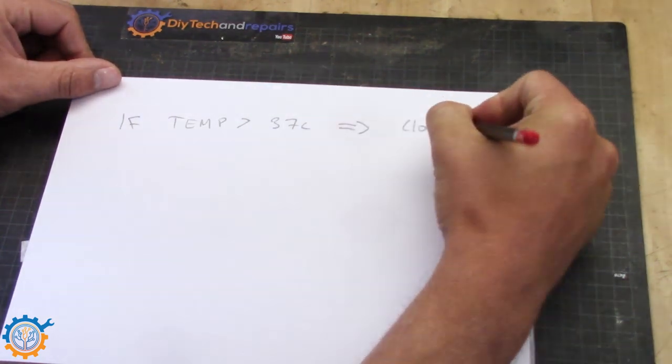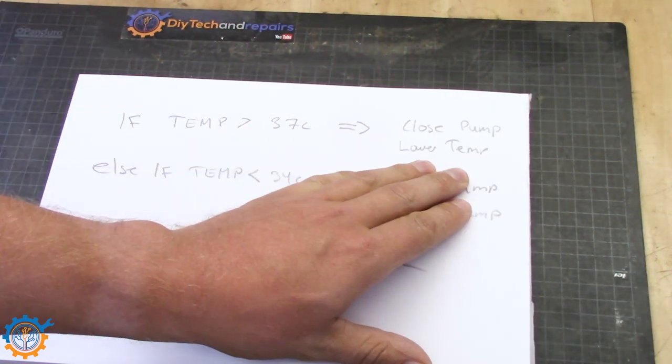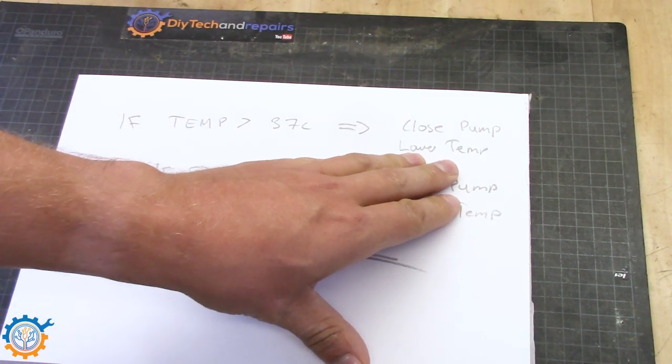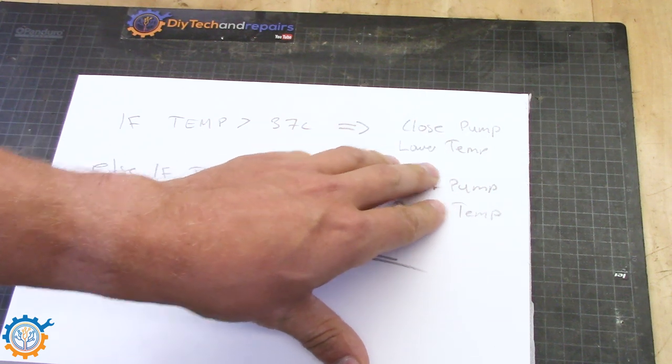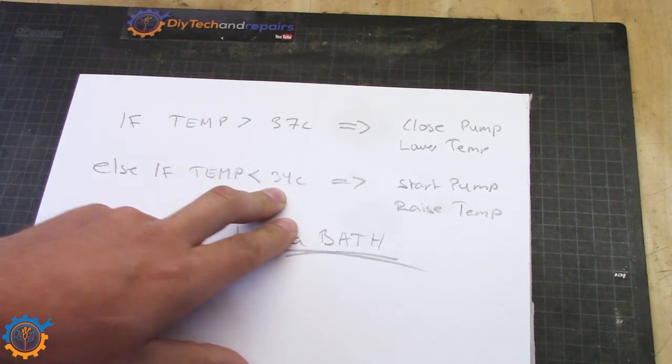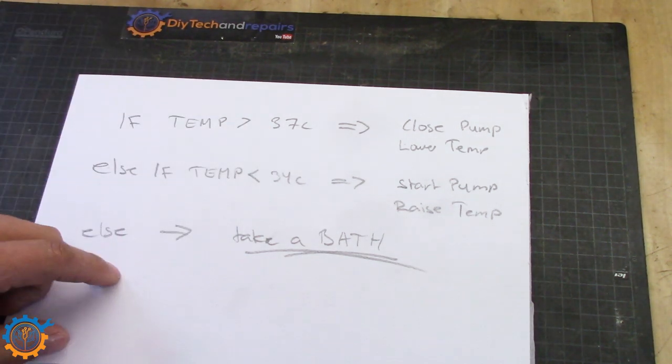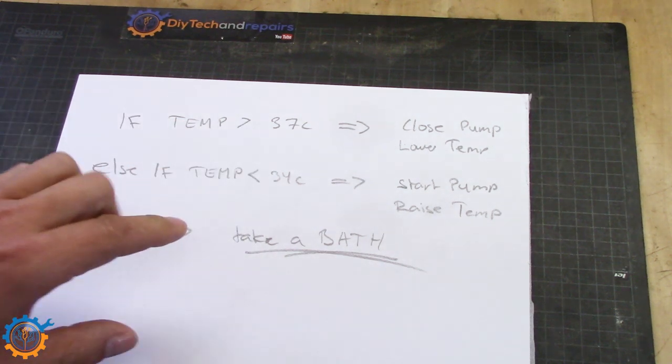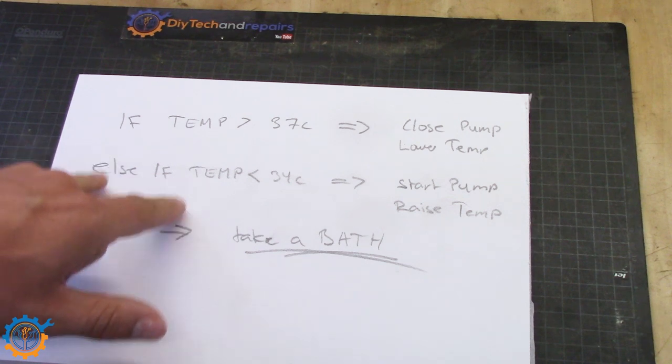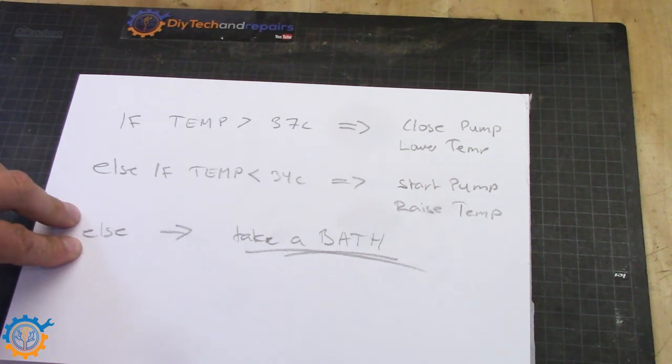Basically what I want to do is if we have temperature above 37°C we will close or shut off the pump and lower the temperature. If the temperature is lower than 34°C I will start the pump and raise the temperature again. I have a hysteresis in between because it takes time until the temperature starts falling or rising again. If they are too close to each other it won't work that great.